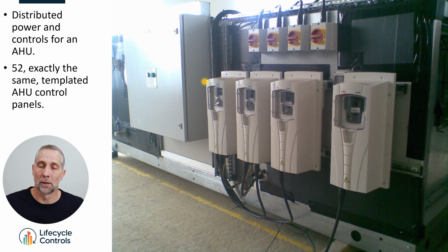What I did work out was that the AHU is sitting there for 3 months early anyway. Look at this one, it's still on a block, a wooden block. There's wooden blocks on here. That's how early this is. For AHU offsite manufacturing, it's not worth it. The AHU sits there for 3 months. Just get 2 electricians with a trolley, push the trolley up, put the VSDs on the isolator, and start the installation with the power and controls 3 months early.